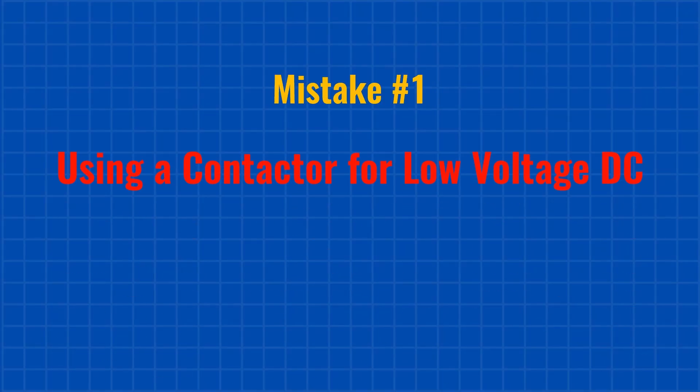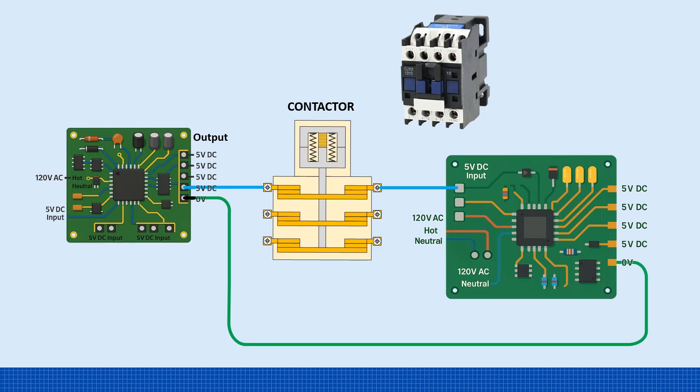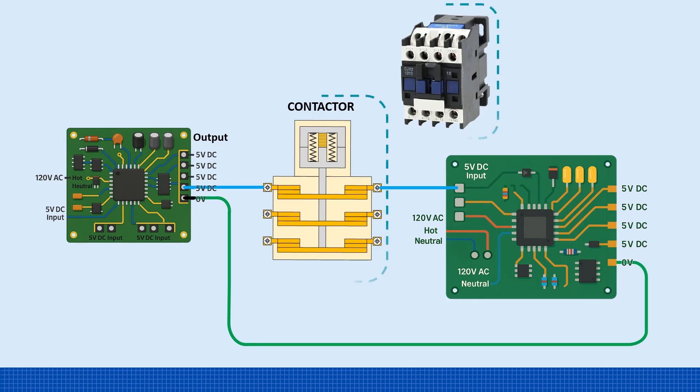Mistake number one. Using a contactor for low-voltage DC. I've seen this issue in control panels far too often, even in well-built systems. In some designs, 5 to 12 volts DC from an electronic card is routed through a contactor and then into a PLC or another device.